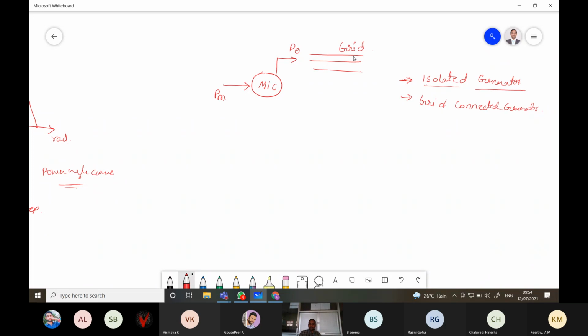Okay. So in a grid connected generator, what happens? The electrical power whatever you are generating is connected to the grid. Suppose a fault occurs on the grid. The voltage becomes zero, and if the voltage is zero, the electrical power is also zero. Then the mechanical power becomes dominant: mechanical power increases and electrical power decreases. So both are unbalanced. More power is pushed into the machine. More power is pushed into the machine.